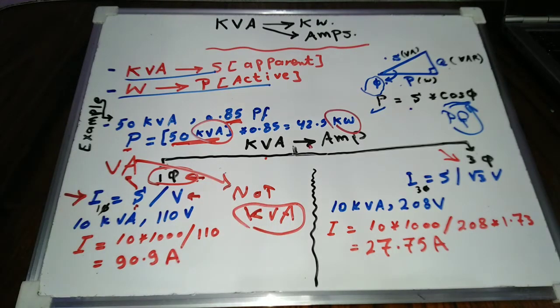If we have a single phase load of 10 kVA and operating voltage of 110 volt, then the current of this load equals 10,000 divided by 110 equals 90.9 amps.